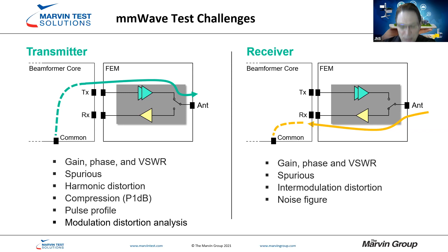So now we'll move to the system level and discuss the challenges test engineers face when transitioning to millimeter wave production test. Basic interconnects and cabling are almost an afterthought when you're dealing with many low frequency applications. But with millimeter wave frequency, there are many factors that contribute to measurement error, and each must be carefully considered and addressed.